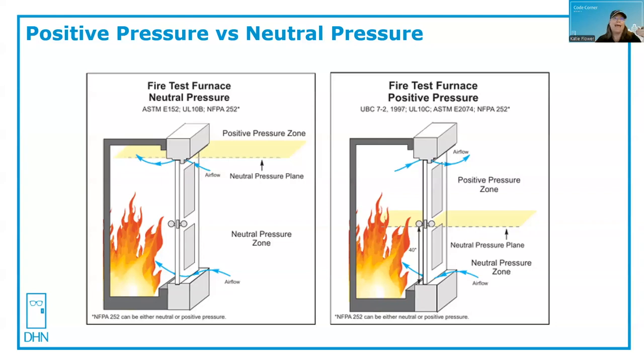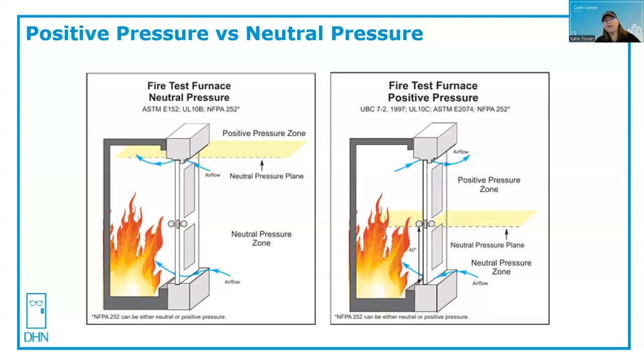The positive pressure fire door test works the same way — the gas is on and in the first five minutes the temperature in the chamber rises to a thousand degrees. But now instead of ventilating the hot smoke and gases out the top like a chimney, it forces the neutral pressure plane to 40 inches above the sill, which is the line of thermal discontinuity. If you ever look at a building after it's burned, the lower 40 inches of the walls and floors are virtually untouched by fire and smoke, but the upper portion is all black and spackled. That lower 40 inches is relatively clean from hot smoke and gases.